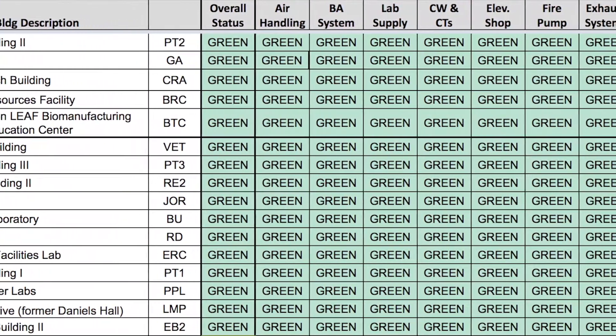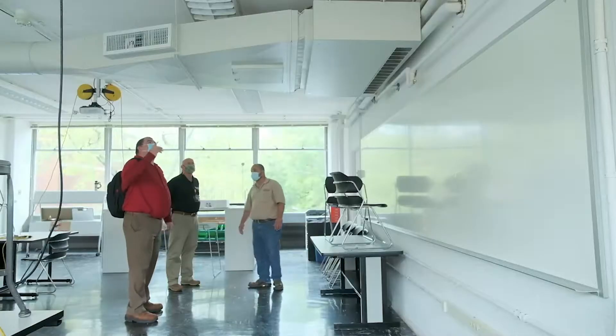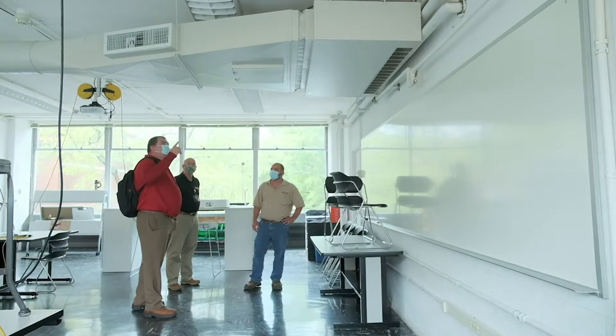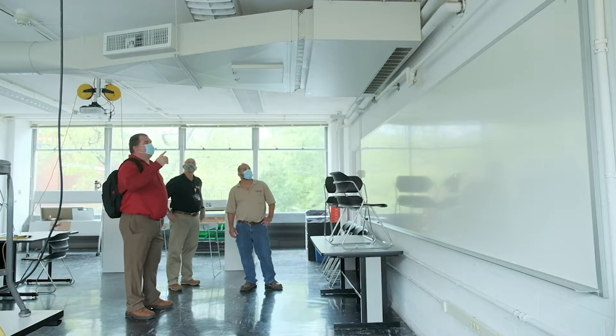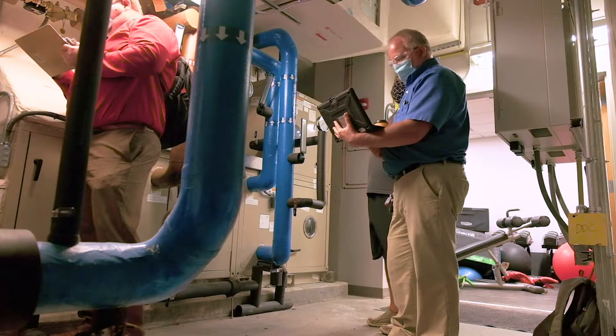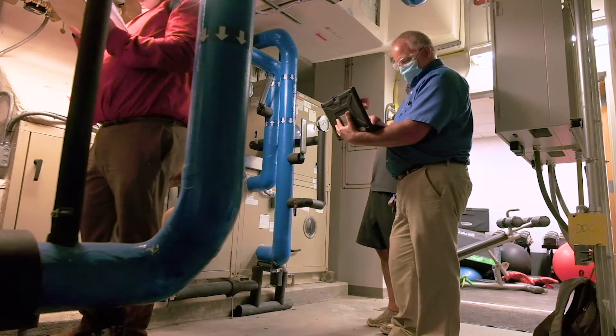We've implemented several specific things to improve the indoor air quality on campus. We've disabled the energy conservation measure that would have reduced the ventilation rates, so we can maximize the amount of outdoor air ventilation to the spaces. Additionally, we have adjusted occupancy schedules so that the buildings are online a full two hours prior to anyone coming in, and they're doing full ventilation then.